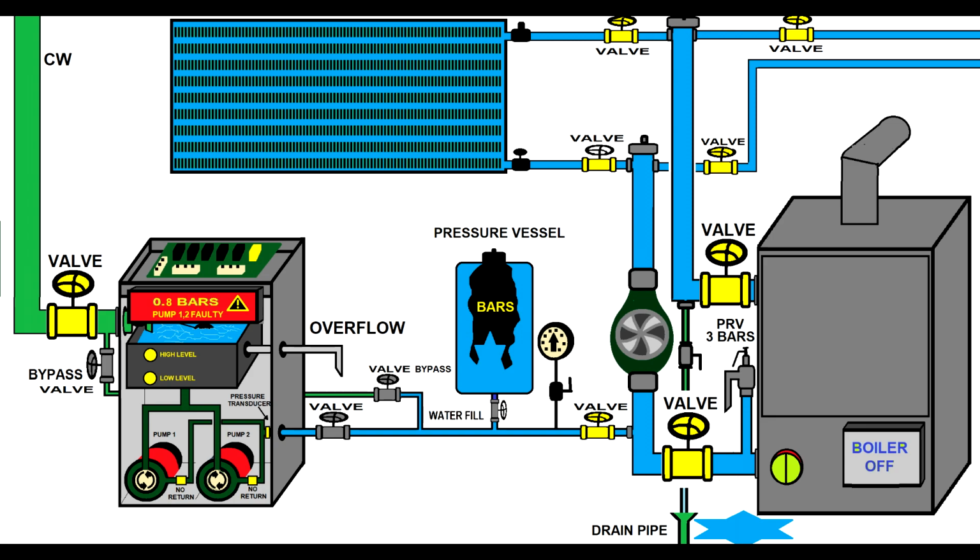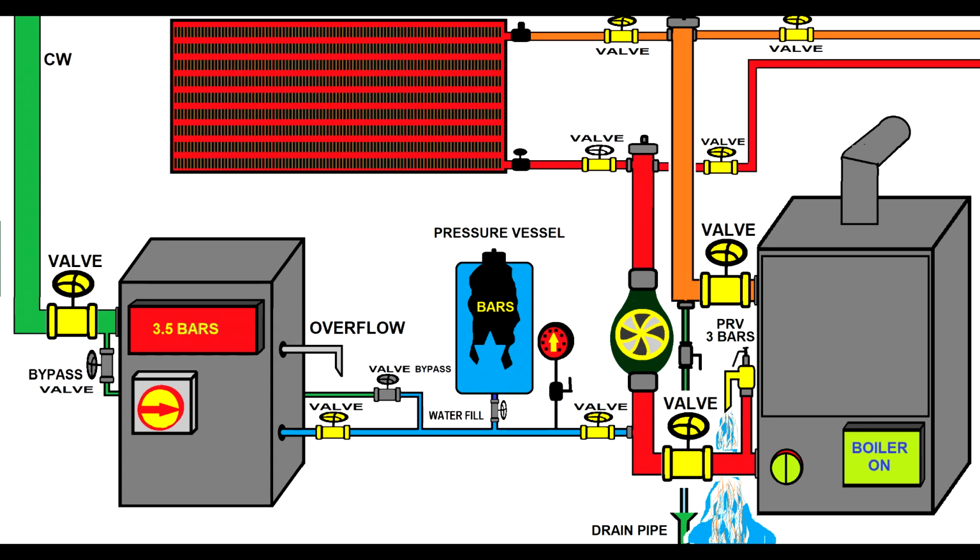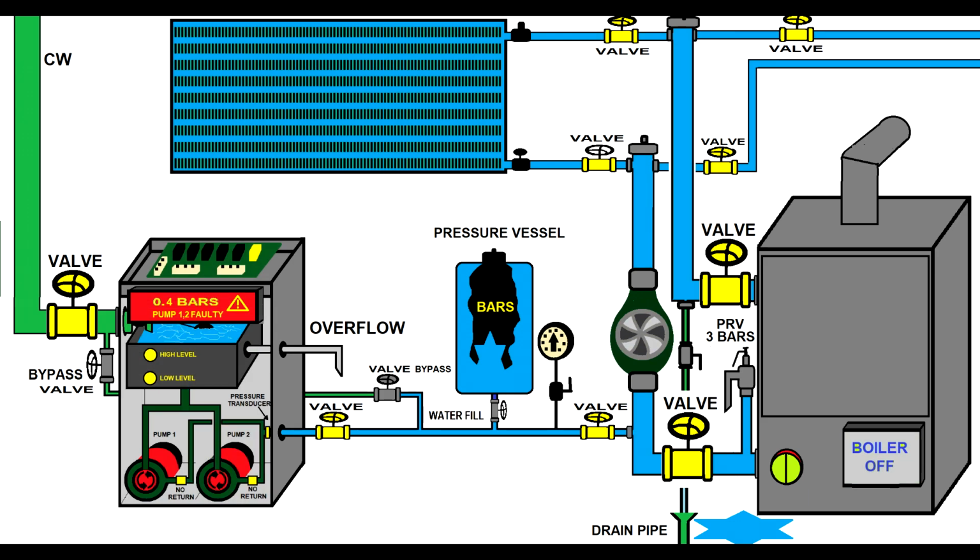That's why you have to be very careful with your colleagues. Sometimes they play heroes, they tell nobody the pumps are broken. So you fill the system again manually, and then the second day you start losing water again, no elasticity in the system, pressure rises too much, and the PRV allows the water to go out. And then the system obviously stabilizes, you run for the day because you can't lose water anymore. Until the second day, when obviously overnight, when nobody uses the installation, the pressure will drop again.